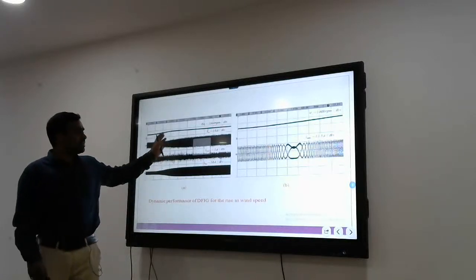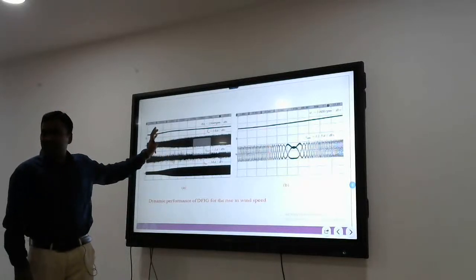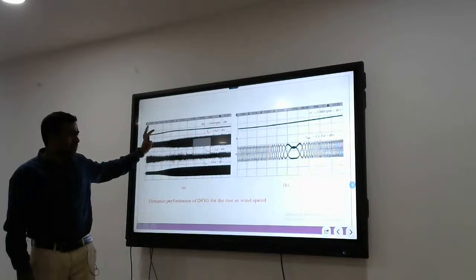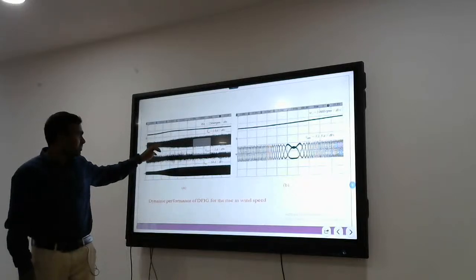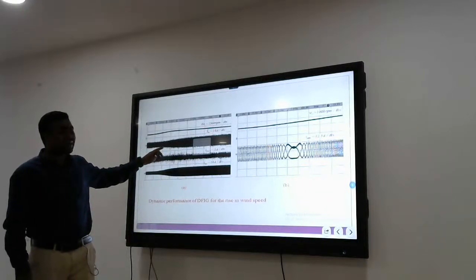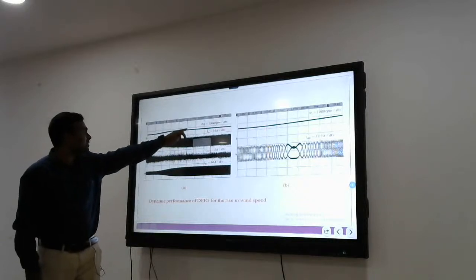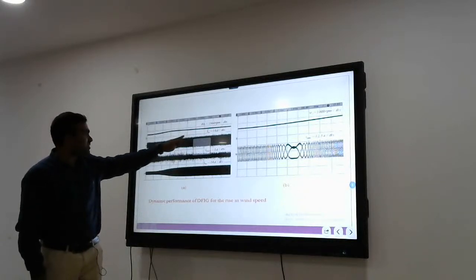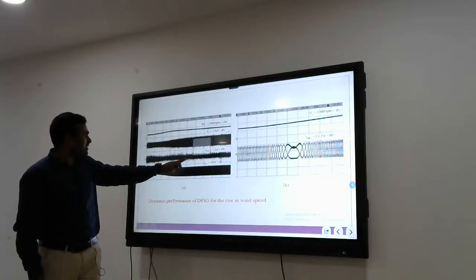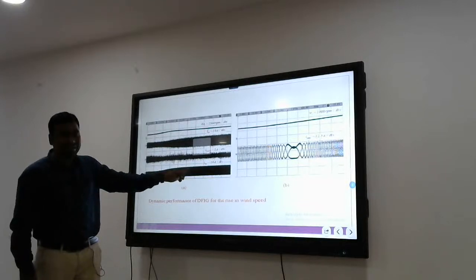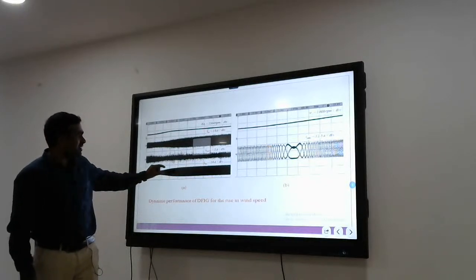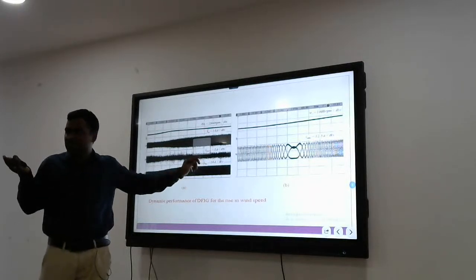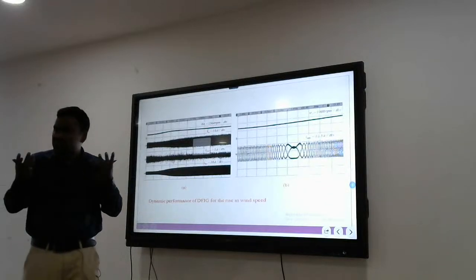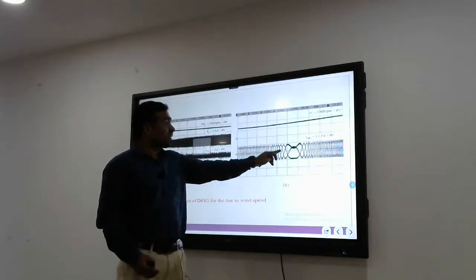If you see here, these previous results are with respect to power. Now these are with respect to currents. This is the change in speed with the change in wind speed. This is stator current, grid side converter current. This is grid current. The grid current started increasing. So the grid voltage is fixed. As current increases, power increases. Okay, this is rotor current.